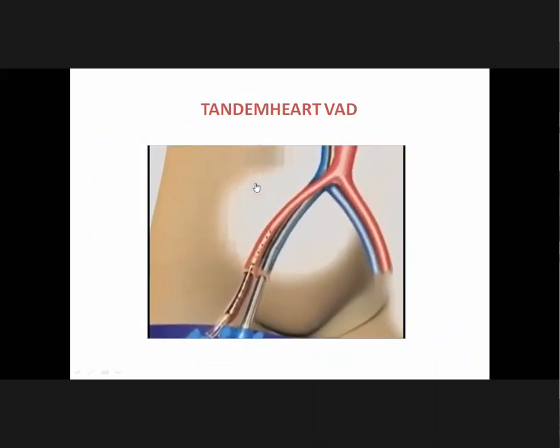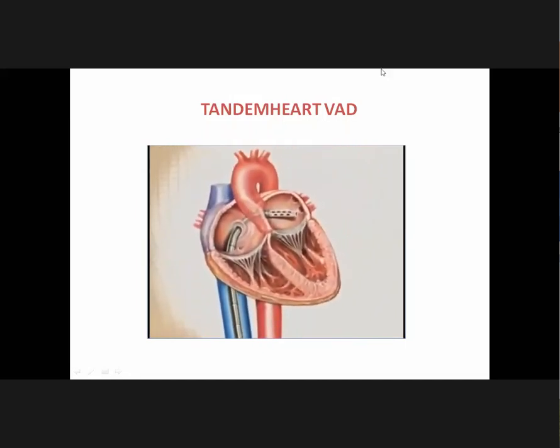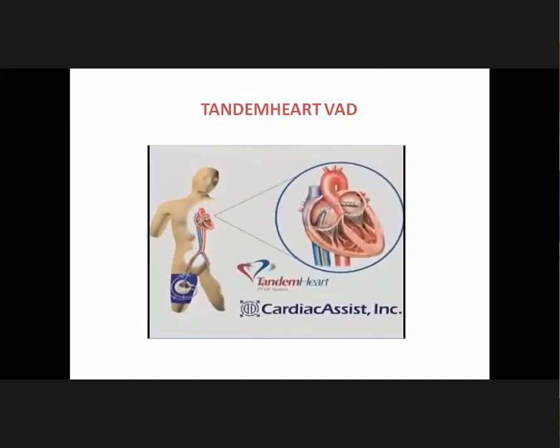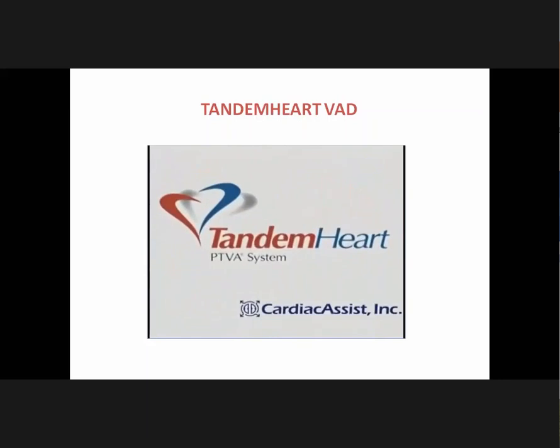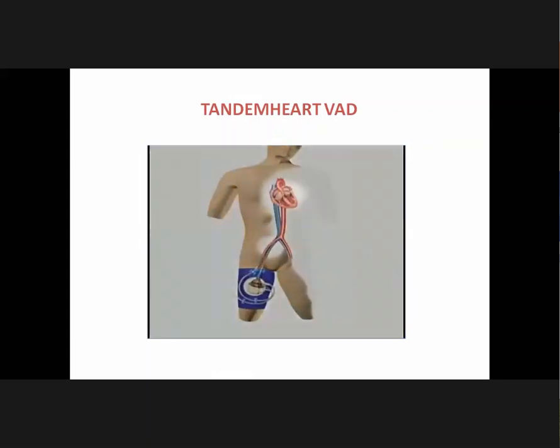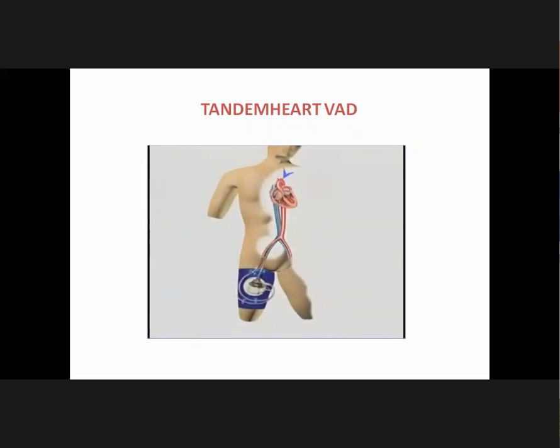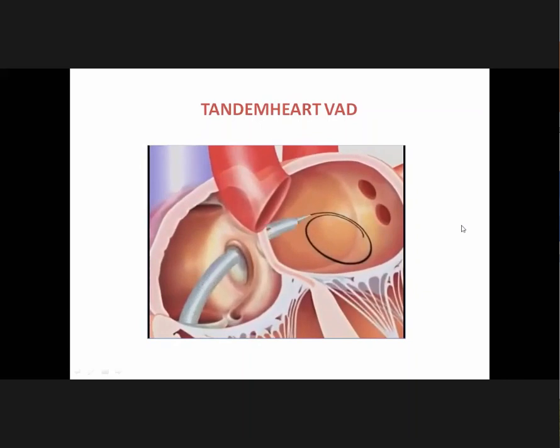In patients requiring extracorporeal circulatory support, evidence suggests earlier deployment is a critical determinant of success. Early support promotes cardiac recovery. The Tandem Heart system can provide up to 5.0 liters per minute of cardiac output. Preload reduction and systemic perfusion are achieved through left atrial to femoral artery bypass, with access from the femoral venous and arterial system. Oxygenated blood is drawn from the left atrium via a drainage cannula and returned via one or two arterial cannulae. The Tandem Heart can be inserted in the cath lab or operating room in as little as 30 minutes using a standard transseptal puncture.